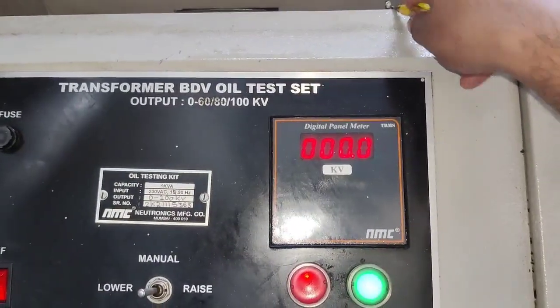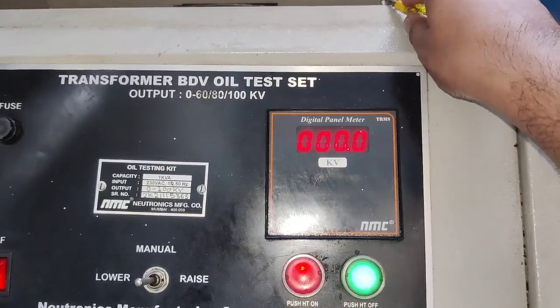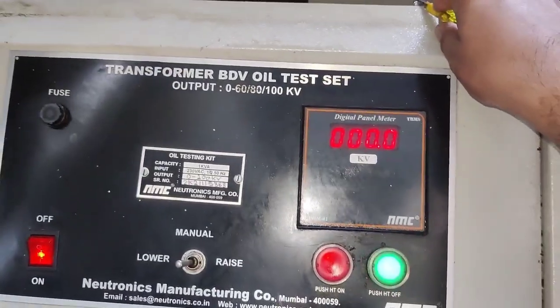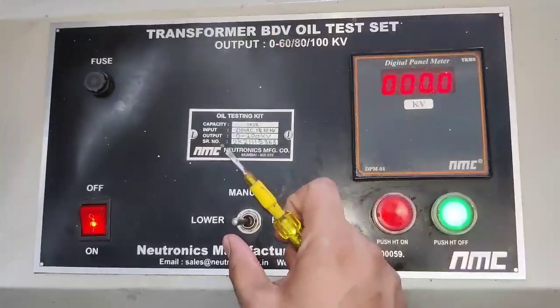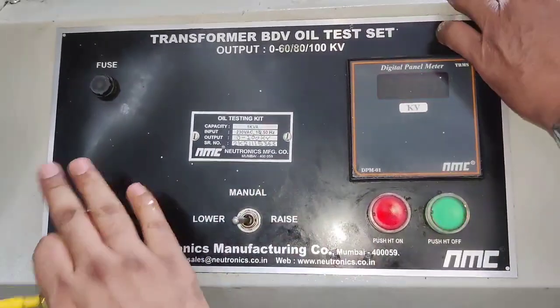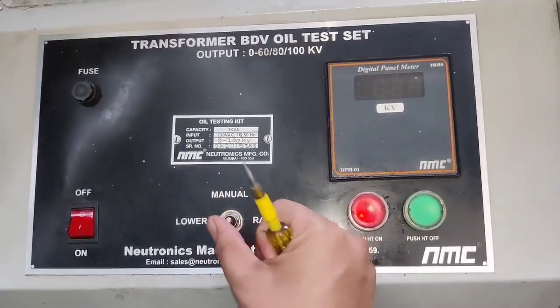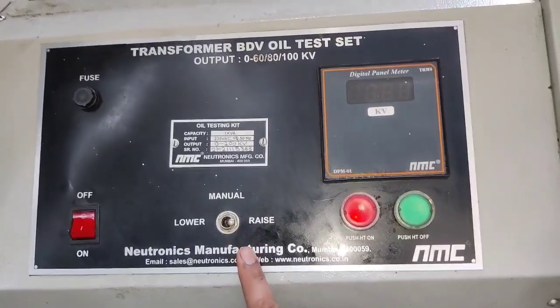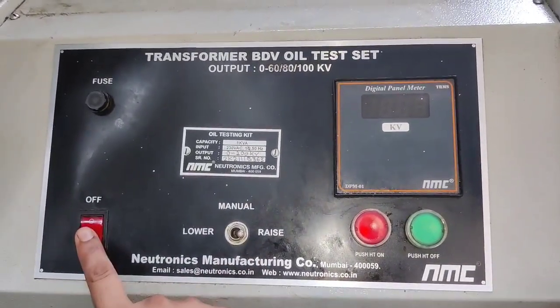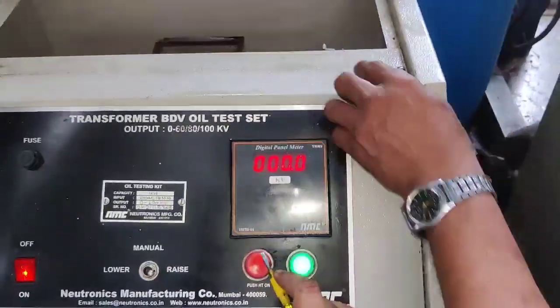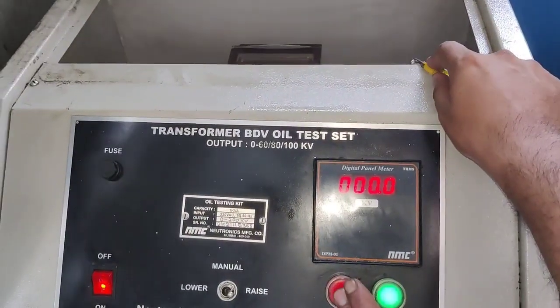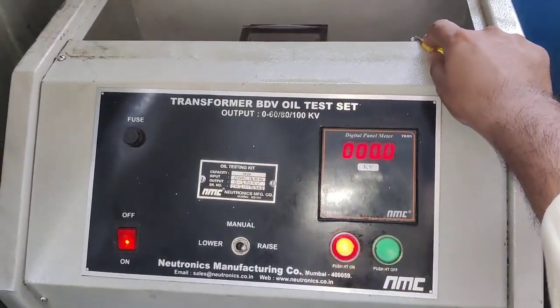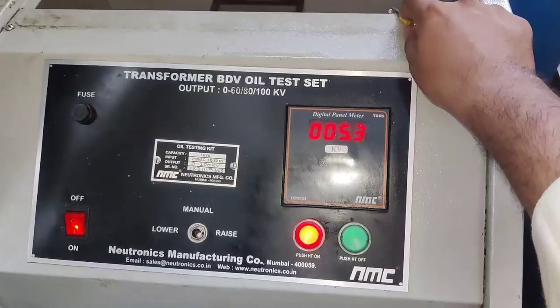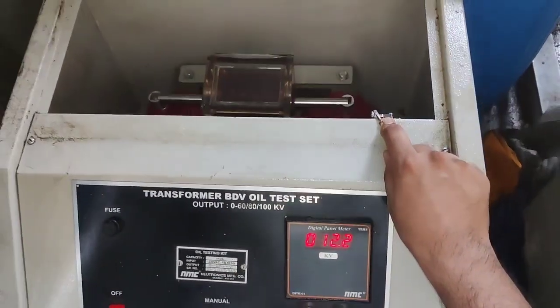If the limit switch is operated, that means the door is closed. So we press the limit switch manually, and we also set this to rise position, the auto position. In raise position, our machine voltage will increase automatically. Now we first operate the limit switch, the start button is pressed, and the HT on button is pressed. Now you can see here, the voltage value is increasing.